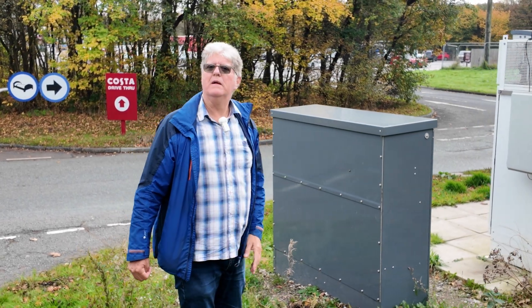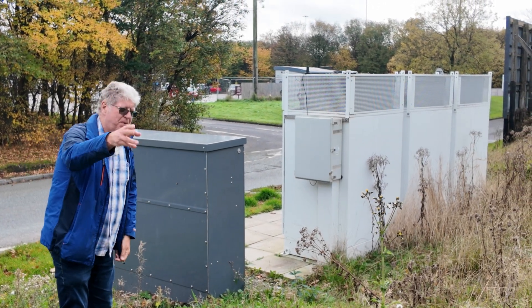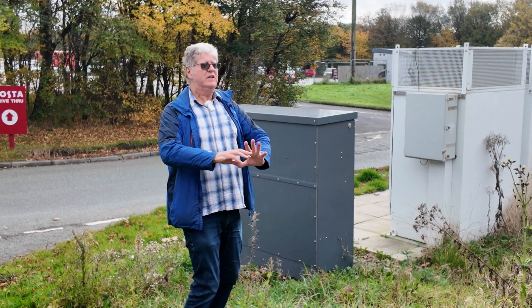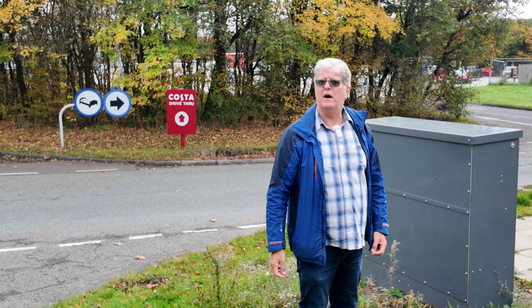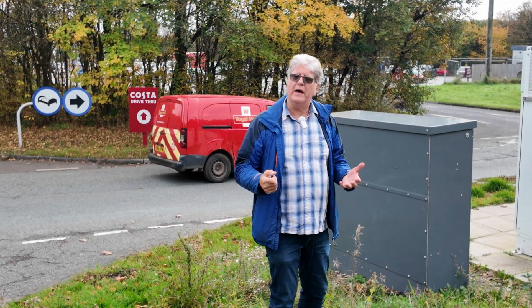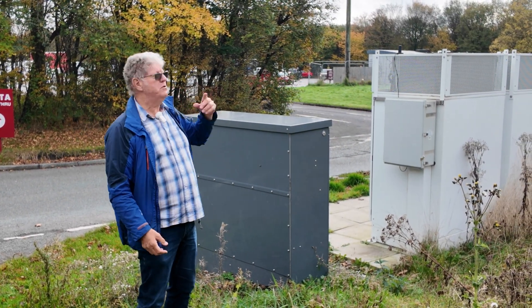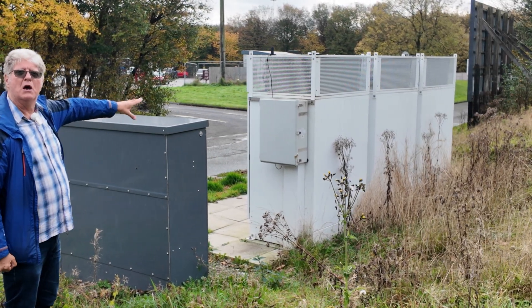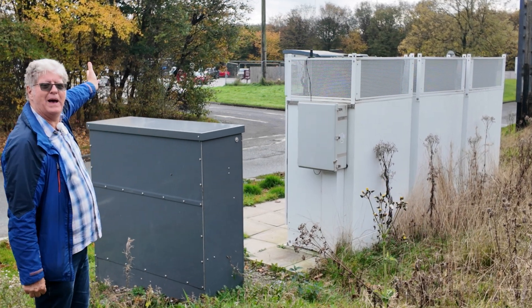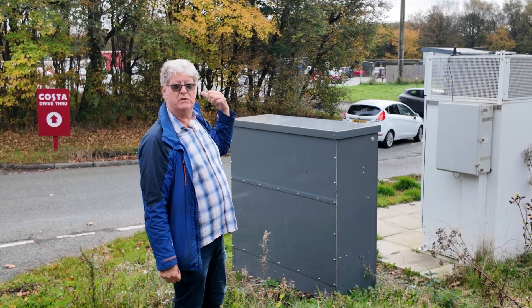These are the cabinets that will drop each of the voltages down. They come in at 470 or 480 for Tesla. I know people will tell me all three phases, 415 — no it isn't. Inside that transformer, when they had it open, I was able to look at it and it's switchable inside from 400 up to 485. And Tesla set their voltage higher than providers like GridServe who are over the other side of the car park. There are three cabinets here. Each of the cabinets will provide enough power to power four of the Tesla V3 chargers — and those are 250 kilowatts each.